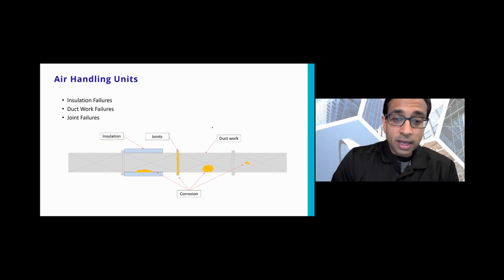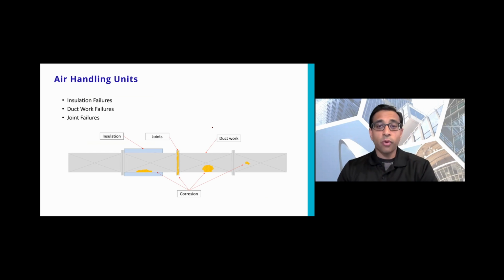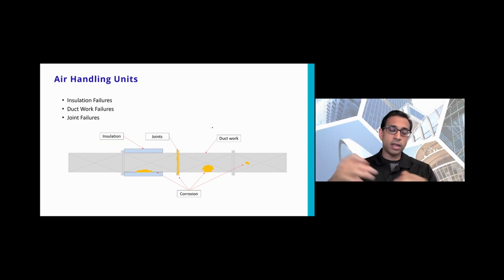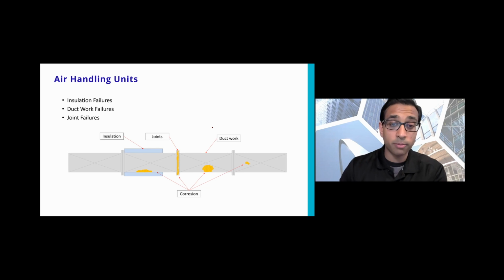In this case, the biggest problem we see is the insulation. I've seen insulation that, even at a year old, is already destroyed. Why? Because you put the insulation on, it starts getting a little crack, water gets in there and starts getting soaked up. Then winter comes, you get freeze-thaw, and it breaks up the insulation. You're going to have problems.